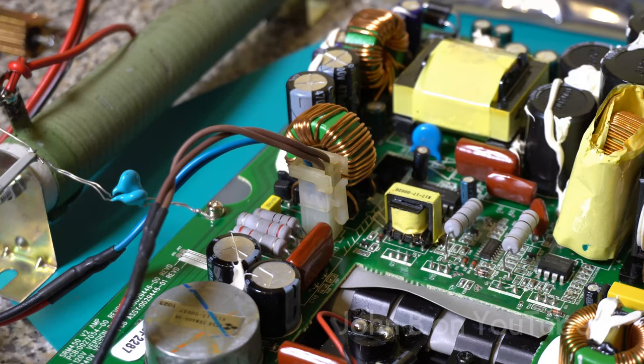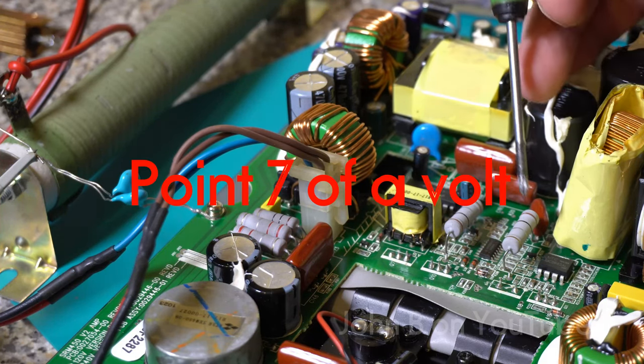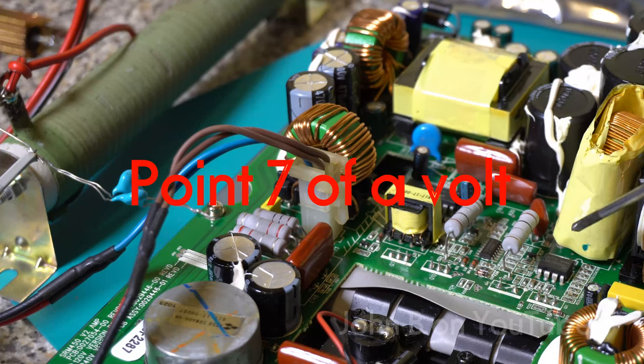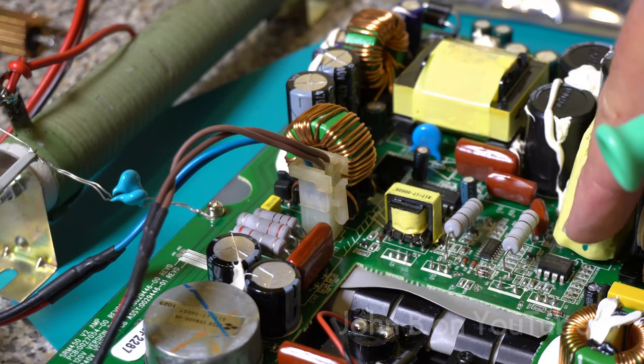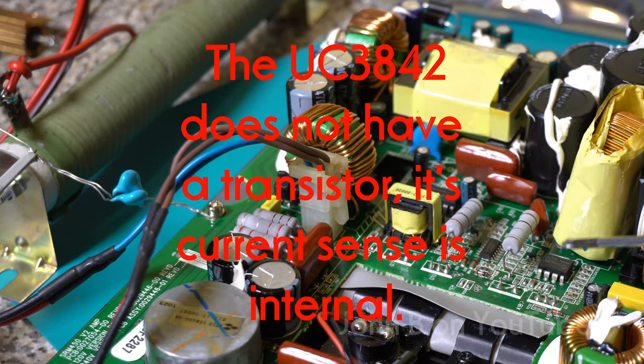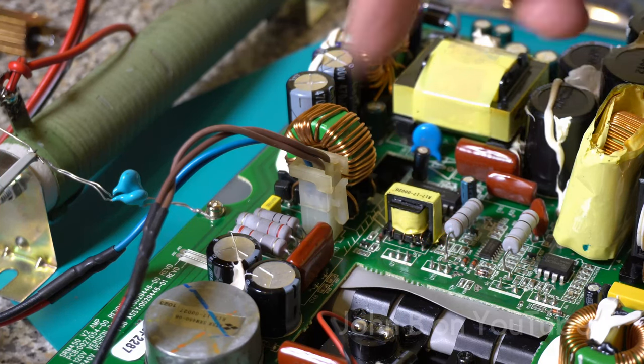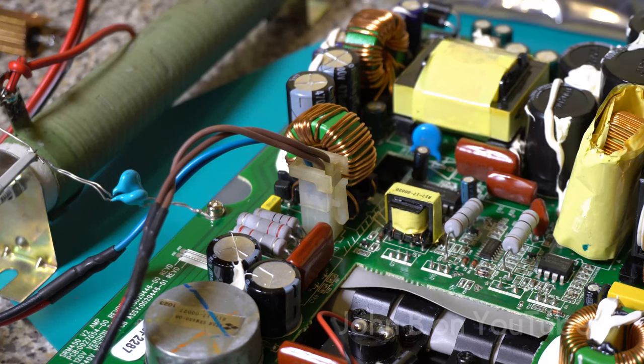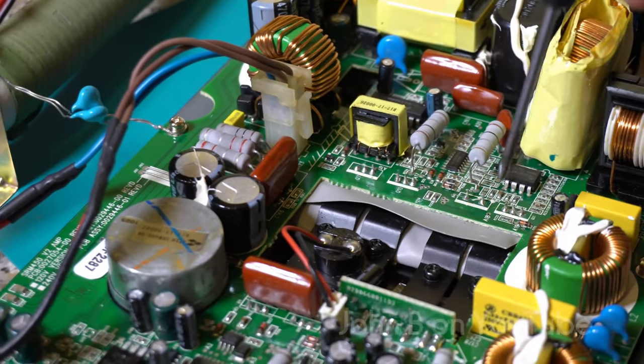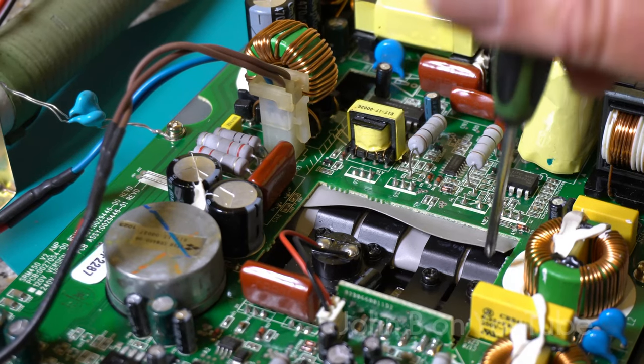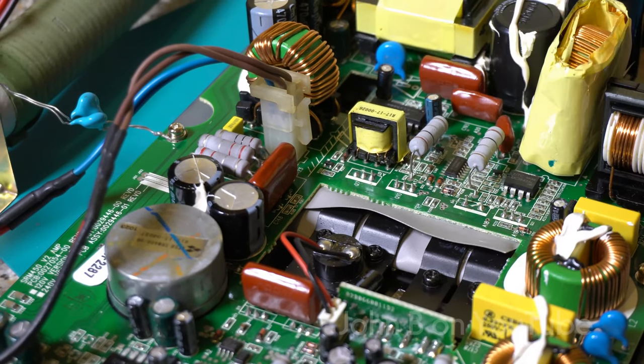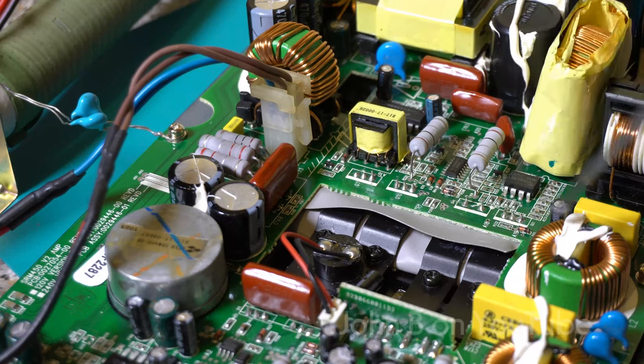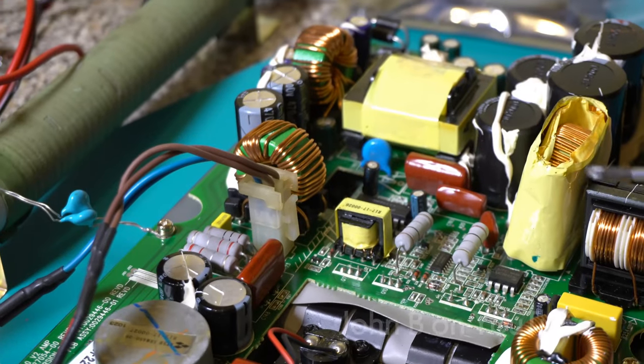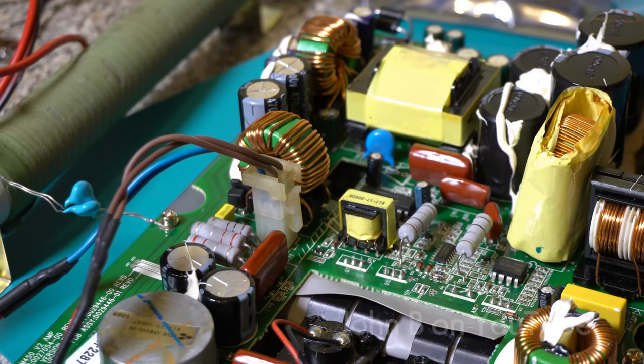So this starts limiting the current at point 7 of a volt peak to peak. Similarly with this circuit, 1 volt across this 0.1 ohm, little transistor underneath, it starts knocking off pulses on this PWM controller. So with these two resistors, these circuits protect themselves, until, of course, you get something like gate erosion and this FET under here just decides to go short circuit. Common fault.